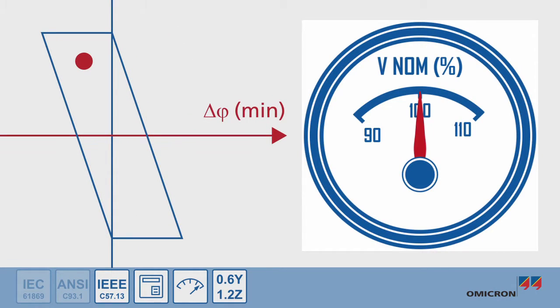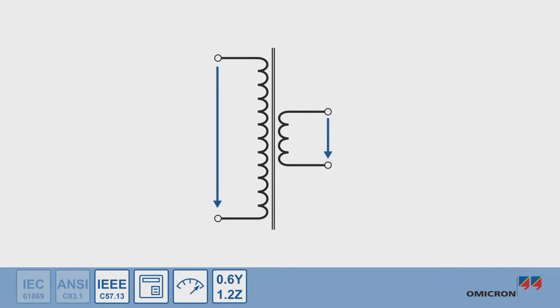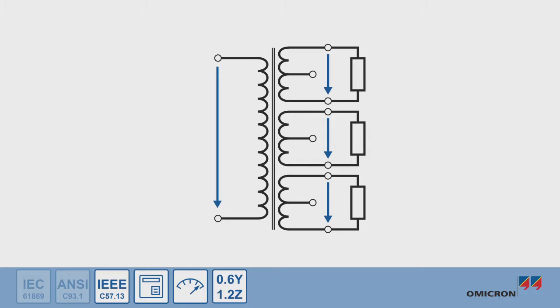The transformation accuracy of the transformer must stay within these limits for voltages ranging from 90 to 110% of nominal voltage. Accuracy ratings apply for the total burden of voltage transformer even if one of its windings is tapped or if it has several secondary windings.